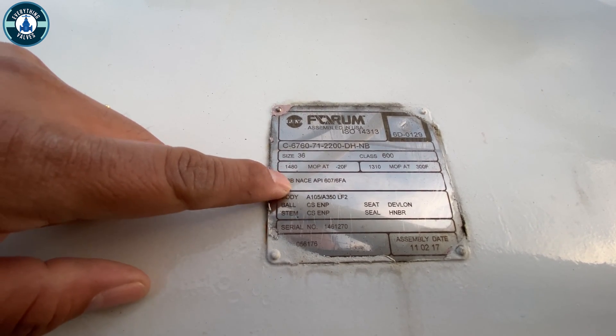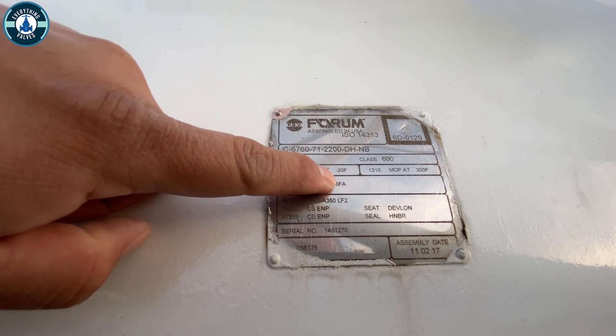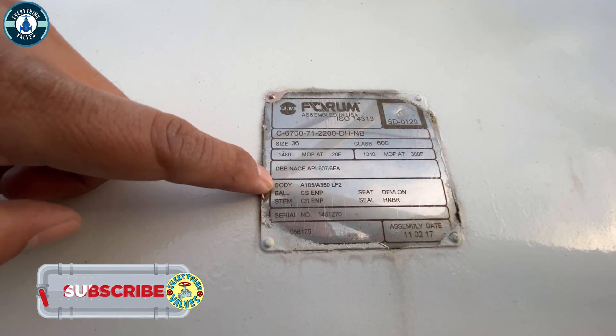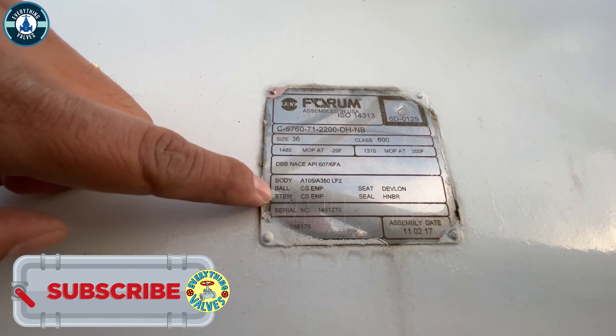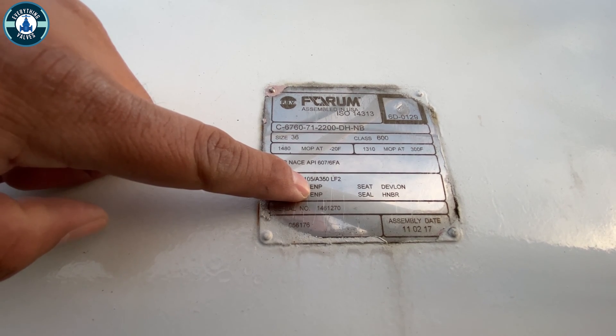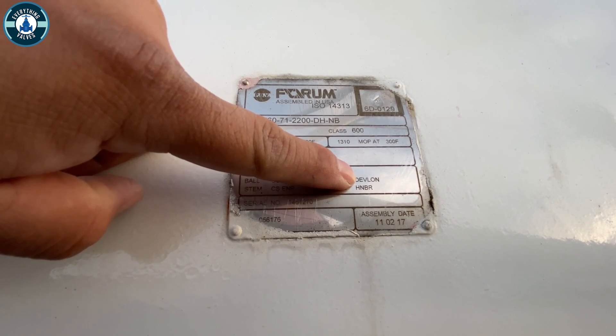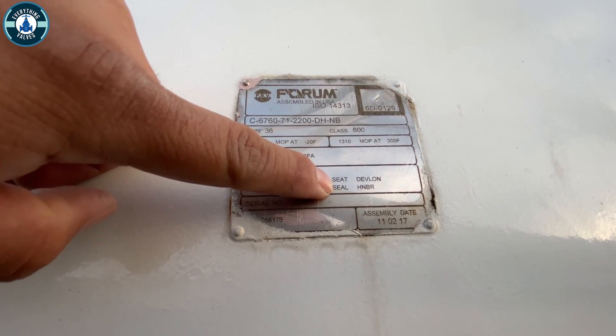This right here tells us it's a double block and bleed. It's API 607, 6FA fire safe. Looking at the materials: the body material is going to be A105 dual certified LF2. The ball and stems are carbon steel ENP coated — ENP stands for electroless nickel plating. The seat on this valve is going to be Devlon, and it's going to have HNBR O-rings or seals.